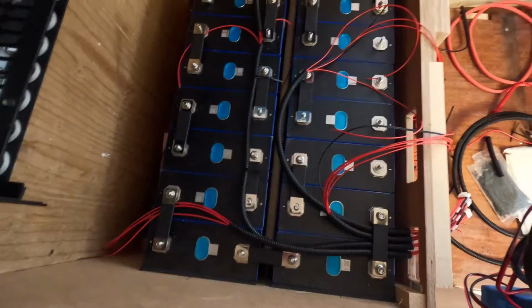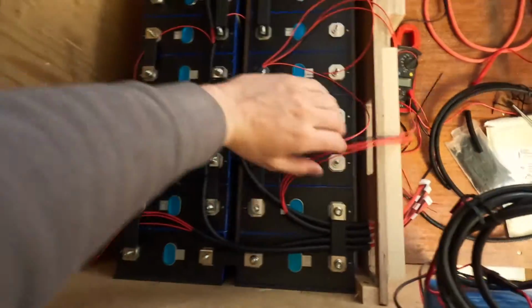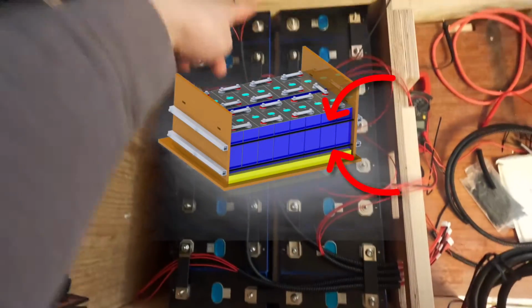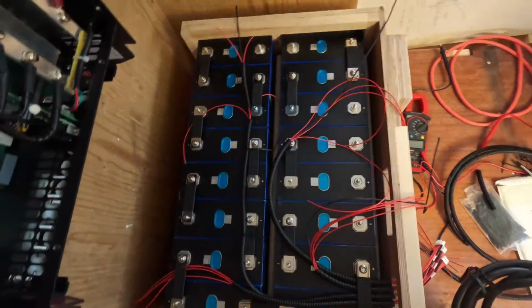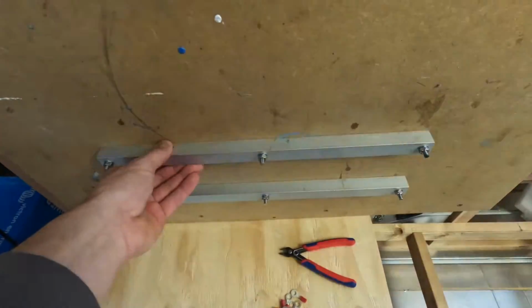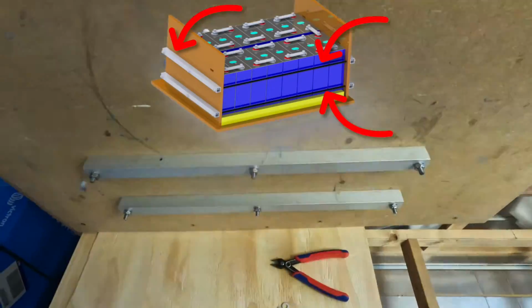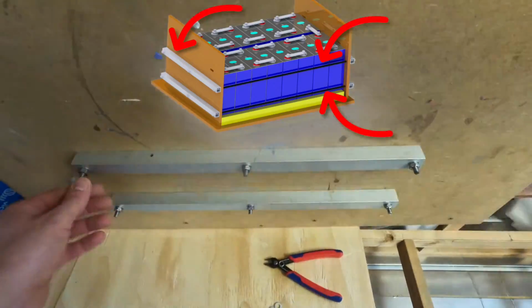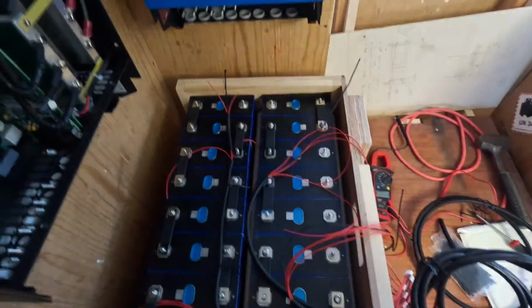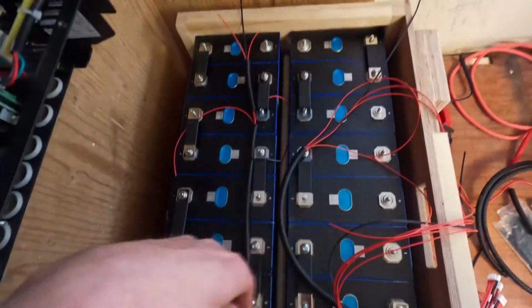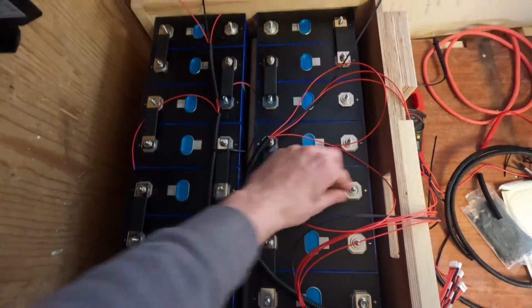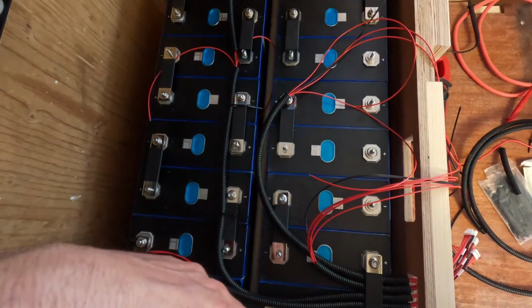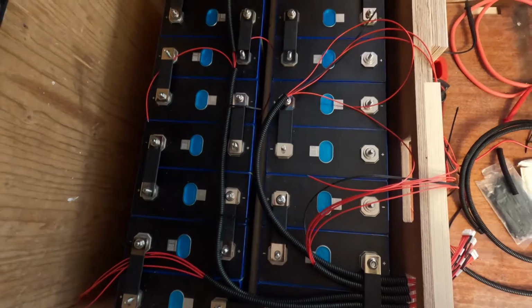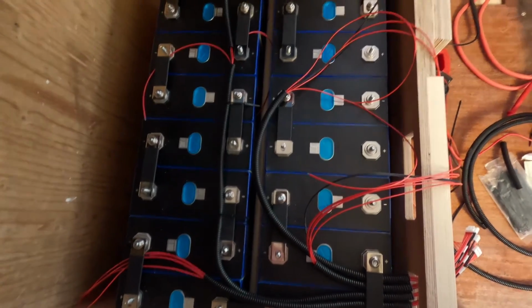It's probably a bit hard to see, but in the middle here and on each side there are two threaded bars going straight through all the cells to a plate on the other side with aluminum profiles like this. The whole package is clamped together with these threaded rods, mainly to keep everything in place, to make sure that the studs are not moving, so we don't have any damage where the bus bars will be connected. It's also supposed to increase the number of cycles you can discharge this type of cell with. But for us, it's mainly to keep everything in place.